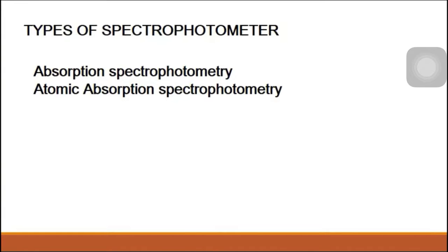At this low energy, the atom can absorb radiation at a narrow specific bandwidth. A wavelength of light specific for the atom is absorbed by the low energy atoms in the flame. This results in a decrease in the intensity of the light measured by the detector.